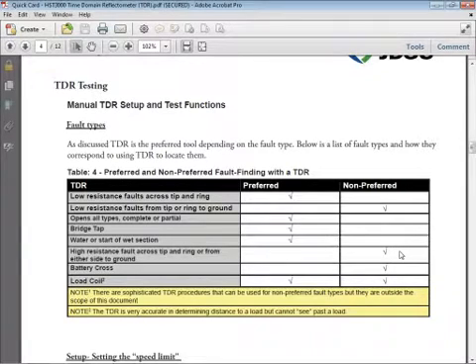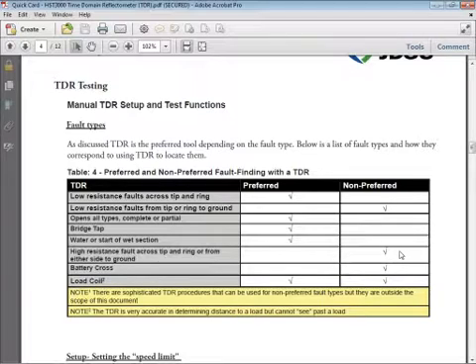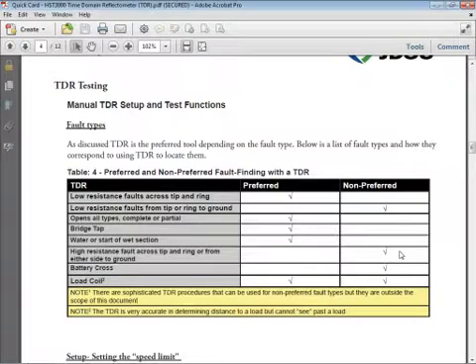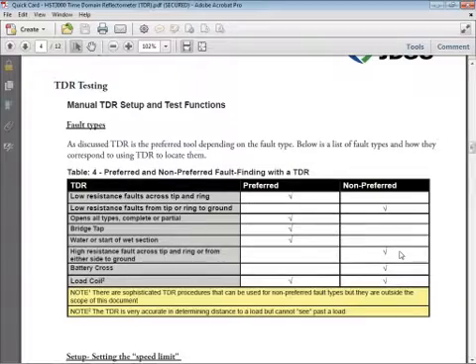Load coil — notice I've got a check mark in both preferred and non-preferred. TDR is certainly good at showing you the first load coil, but it cannot look past or see through the load coil. So therefore, it's sort of limited.